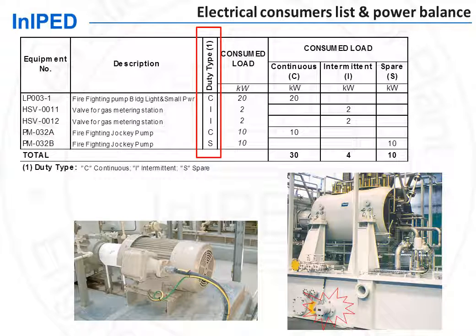The overall power consumption is then calculated by summing the consumed load times what is called a coincidence factor, which will be 1 for continuous consumers, maybe 0.5 or 0.6 for intermittent consumers, and 0.1 for spare consumers. Indeed, for spare consumers, it is still required to consider some power being consumed when this consumer is started while the other one is not yet stopped.